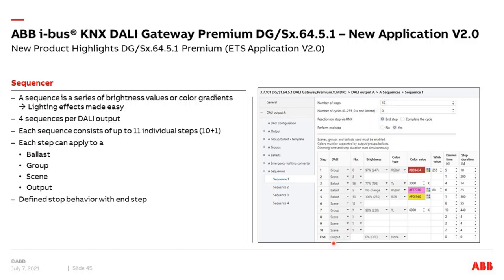The sequencer steps run through from first to last, cycle after cycle. When you send a group address with value zero, the sequencer stops. If 'perform end step' is set to yes, it jumps to the end step — for example switching off the light. The cycle count can also be set to zero for endless running.